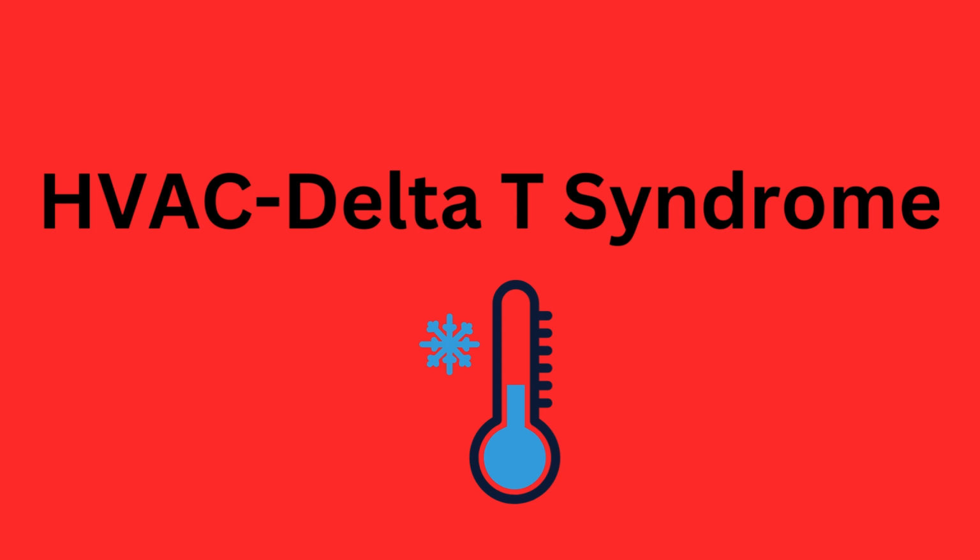Duct issues. Leaks or blockages in the ductwork can alter the airflow and temperature difference. Thermostat problems. Faulty or improperly set thermostats can affect system performance. Improper sizing. An incorrectly sized HVAC system may struggle to maintain proper delta T.